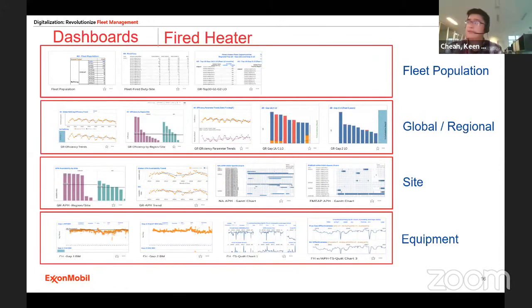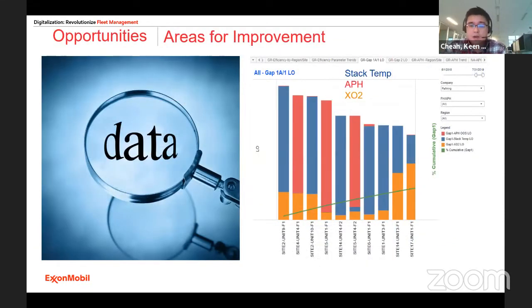Areas of improvement can be easily identified using the tool. For each furnace, one can identify the dominant contributor of the identified gaps: is it because excess O2 is high, or because stack temperatures are high? If excess O2 is high, what's the associated loss? What sites have low excess O2 and no associated losses? Can we reach out to those sites to find out what they've done and implement those steps at our sites?